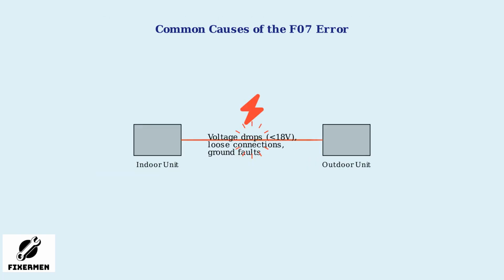Several factors can lead to communication timeouts. Electrical issues like voltage drops below 18 volts, loose connections, or ground faults are frequent culprits. Hardware failures, such as faulty control boards, capacitors, or sensors in the outdoor unit, can also cause the error. Environmental factors, like extreme temperatures or moisture leading to corrosion, can disrupt communication. Even software or firmware glitches can cause communication issues.